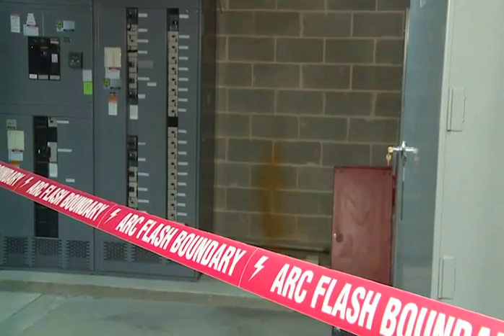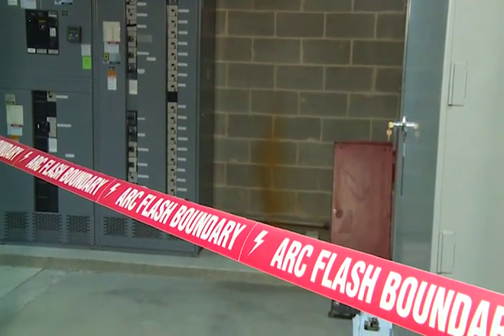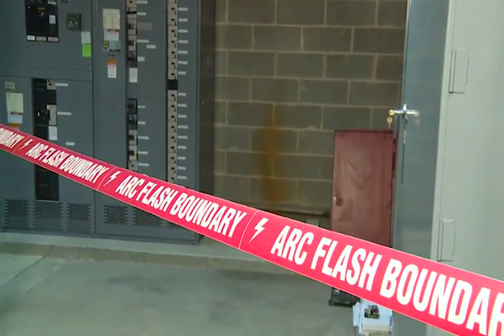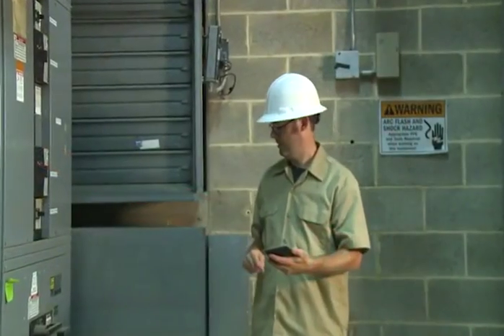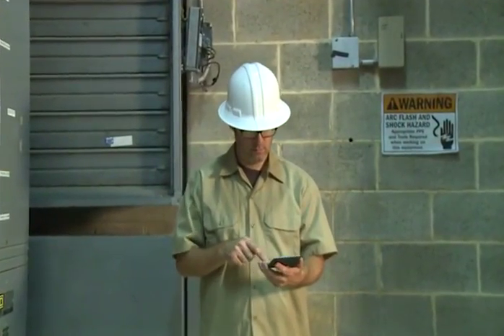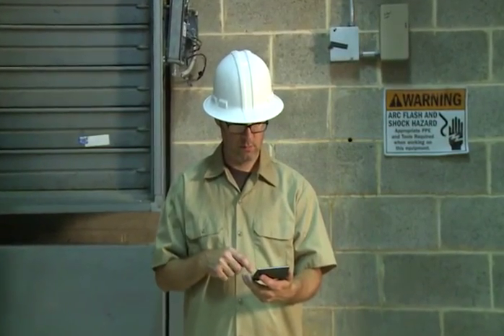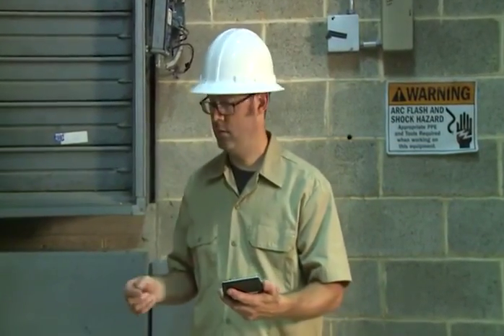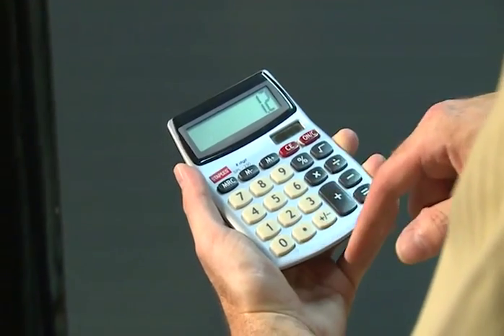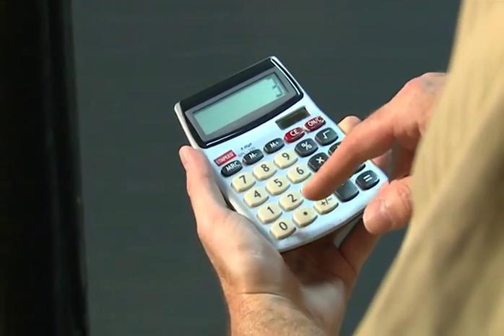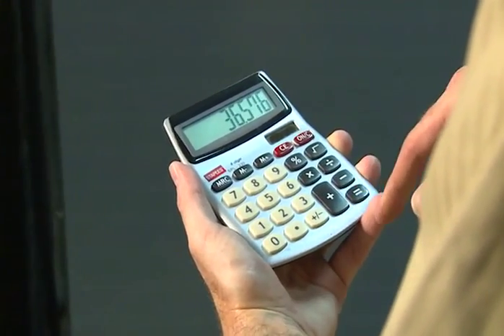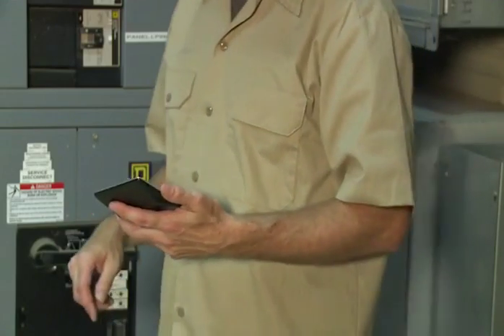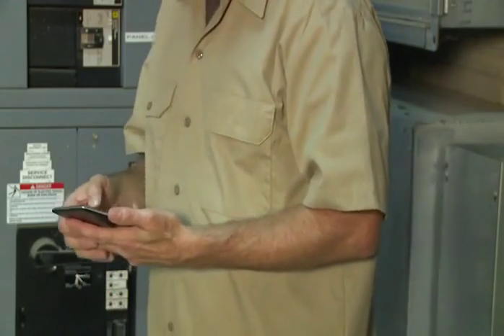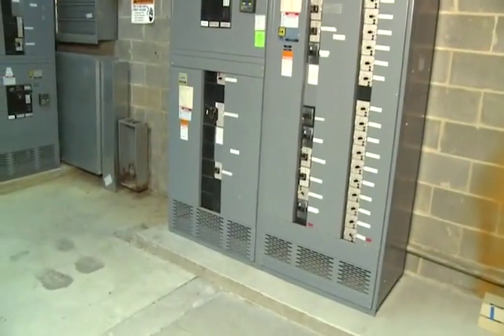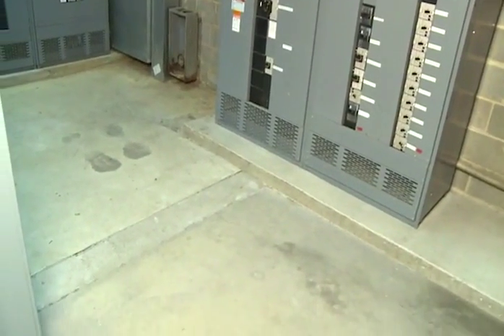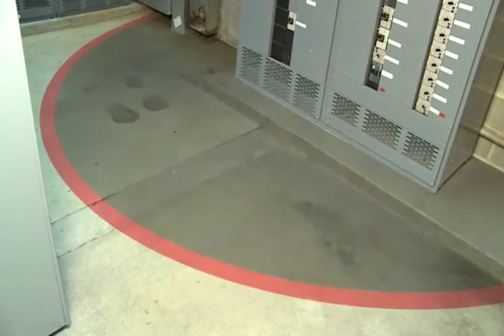Another important step in creating an electrically safe working condition is establishing an arc flash boundary. To determine where this boundary should be, you calculate at what distance from the equipment the incident energy of an arc flash would equal 1.2 calories of heat per square centimeter. 1.2 calories per square centimeter is the heat value that will cause a second-degree burn on unprotected skin. This second-degree burn distance is where the arc flash boundary will be set up.